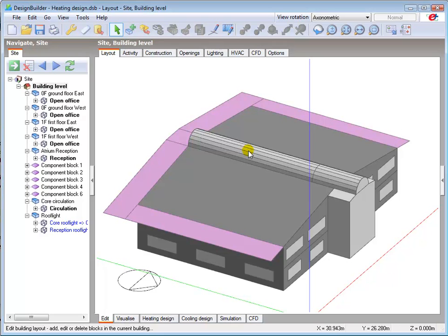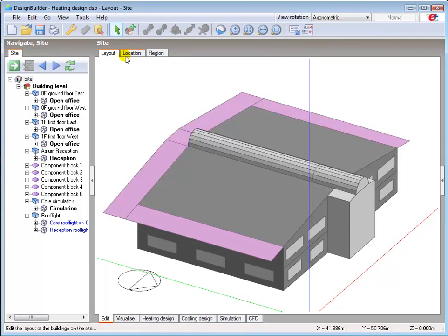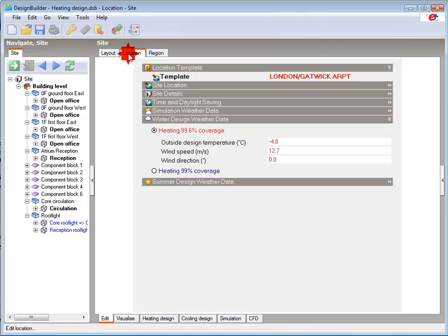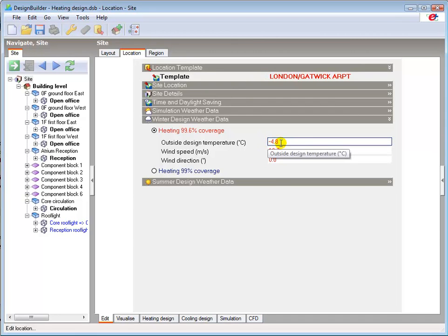Before opening the heating calculation tab you must ensure that the correct location is set. You can check this at site level in the location tab and here you can see that the London Gatwick Airport template is set with an external design temperature of minus 4.8 degrees C.